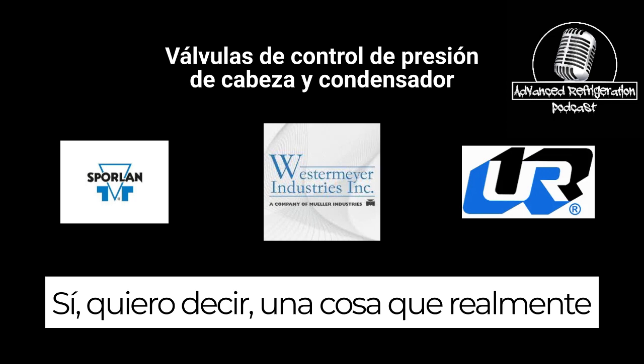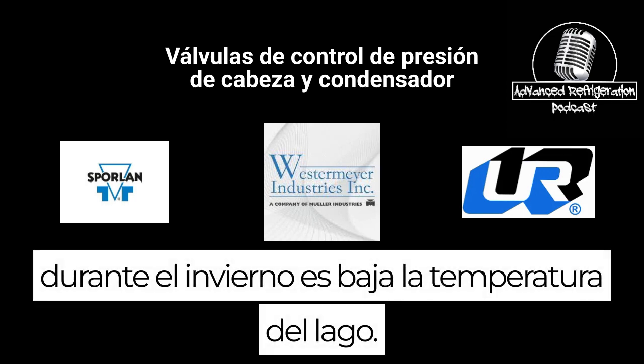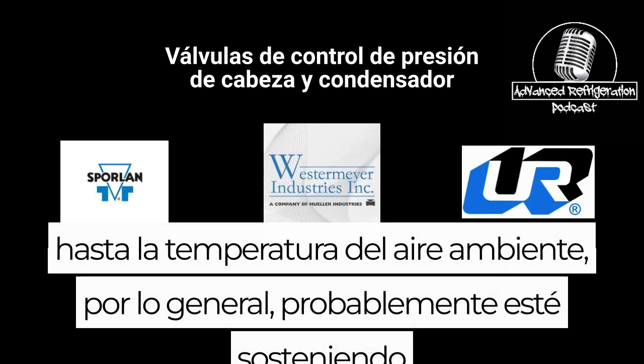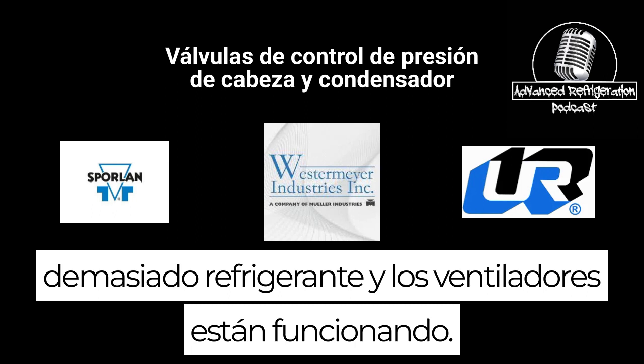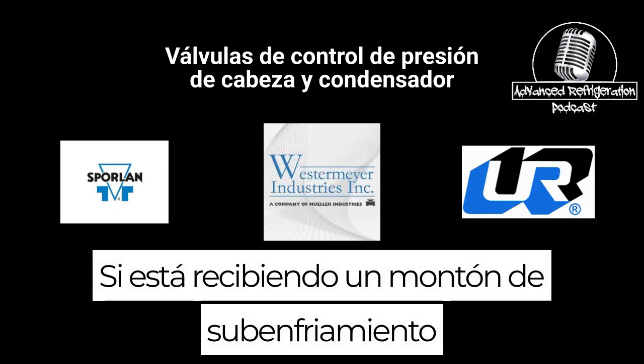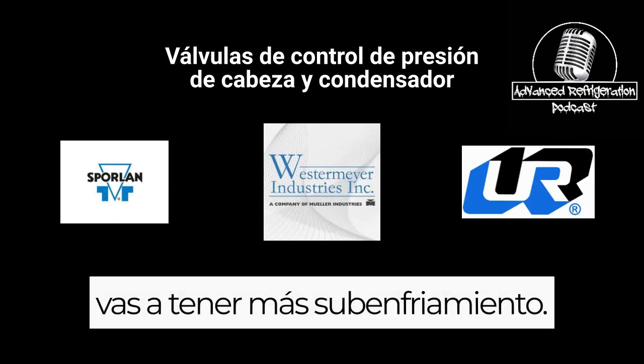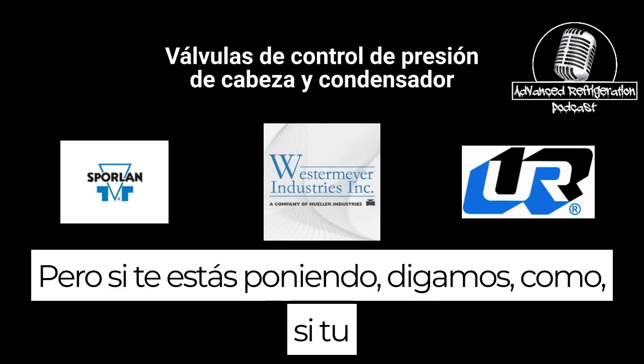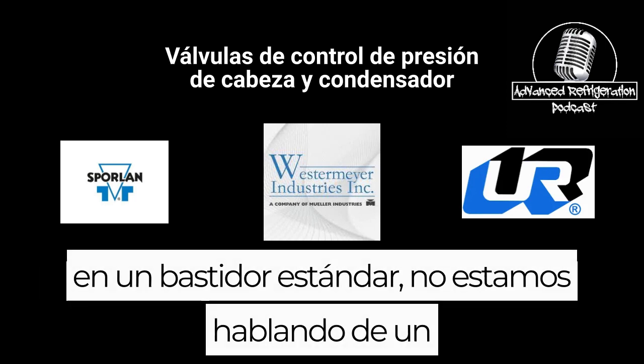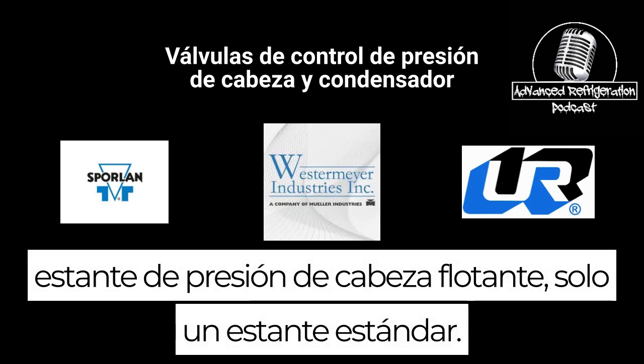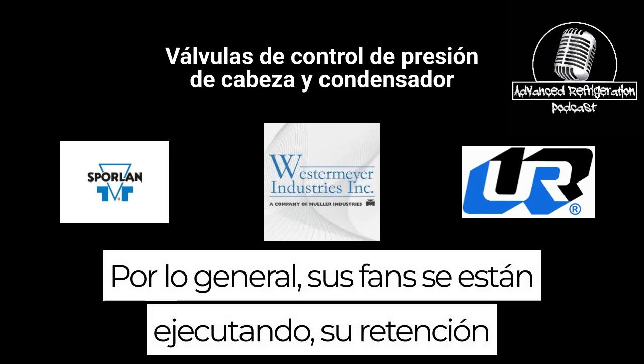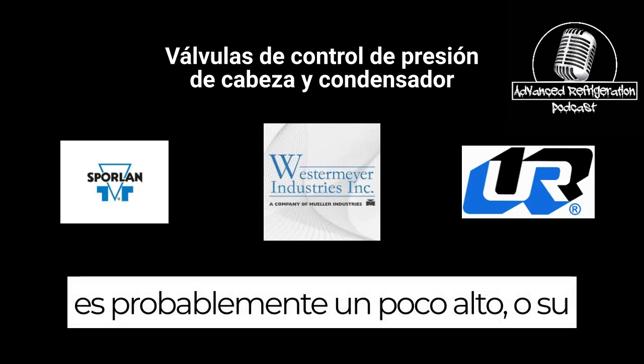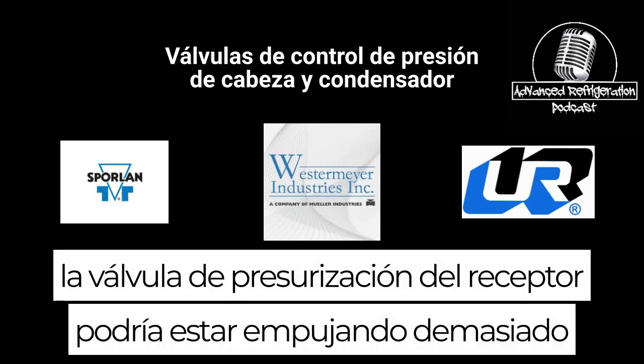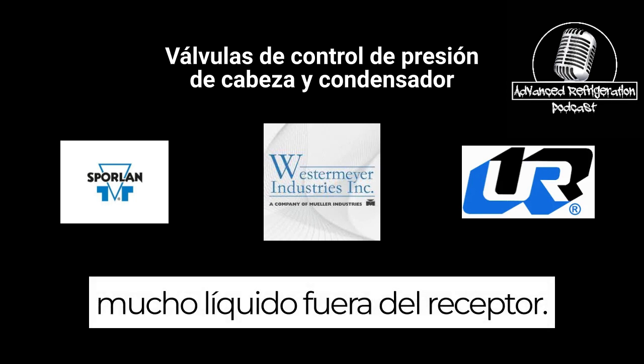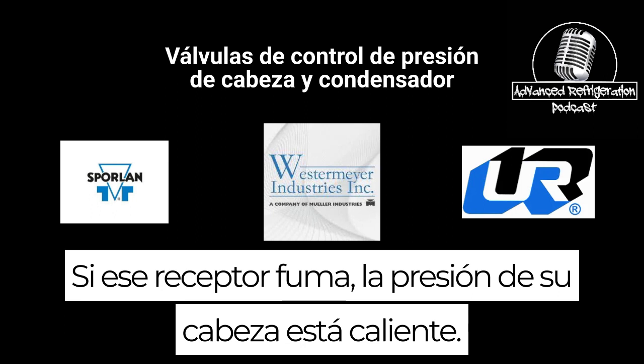One thing in the winter time is drop leg temperature. If your drop leg temperature is all the way down to ambient air temperature, generally you're probably holding back too much refrigerant and the fans are running. If you're getting a boatload of subcooling coming off that roof, yeah, in the winter time you're going to have more subcooling. But if your drop leg temp is down to like 40 degrees on a standard rack, we're not talking a floating head pressure rack, just a standard rack, generally your fans are running, your holdback's probably a little high, or your receiver pressurization valve could be pushing too much liquid out of the receiver.